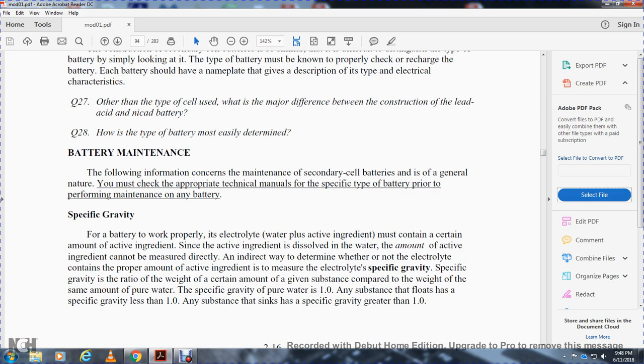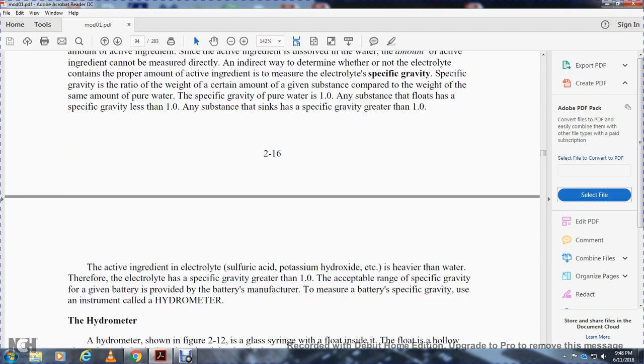Battery maintenance: the following information concerns maintenance of secondary cell batteries. A technician must check the appropriate technical manual for the specific type of battery prior to performing maintenance. Specific gravity: for a battery to work properly, the electrolyte must contain a certain amount of the active ingredient dissolved in water. Specific gravity is the ratio of the weight of a certain amount of a given substance compared to the weight of the same amount of pure water. The specific gravity of pure water is 1.0.